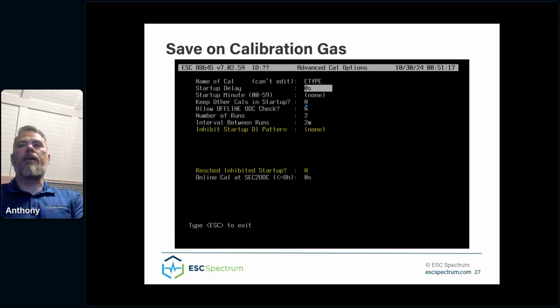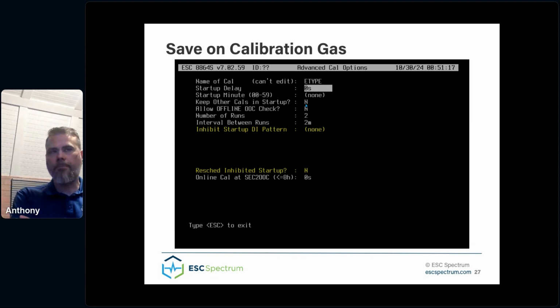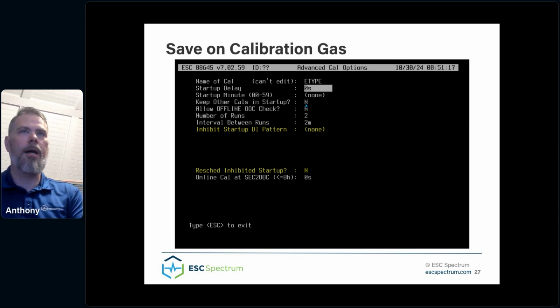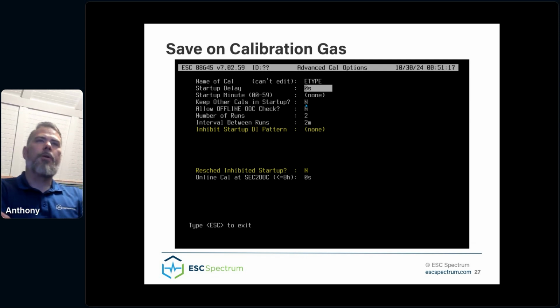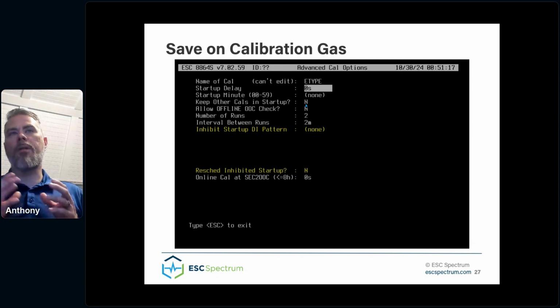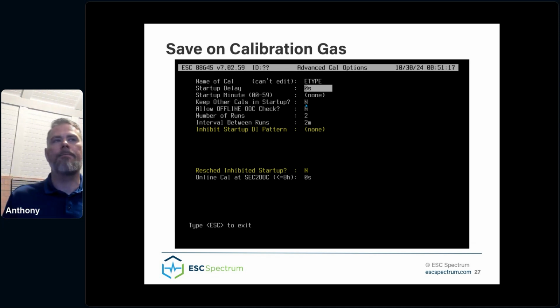Now, to save on calibration gas, we've added some settings to calibrations called inhibit startup digital input pattern and reschedule inhibited startup. I'm going to try to stay mostly high level on this one, it's pretty complex. You have the ability to put in a complex pattern that, when evaluated to true, will inhibit a startup calibration from running.